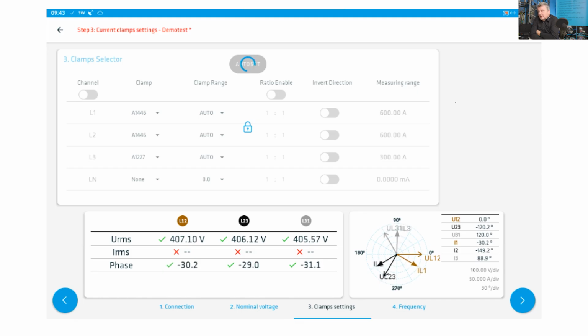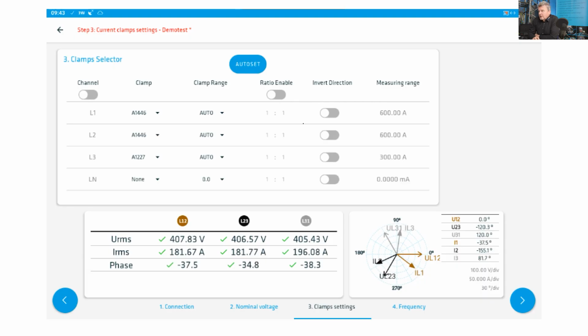This takes up to 1 minute, because the value of the current must stabilize, and we will see the final result in a few seconds. The maximum time depends on the saturation of the electronics and could take up to 1 minute, as I already mentioned. Now we'll wait for the current to be presented. When you select auto range, during the changing of the range it's possible that you will not have some results for a specific integration period, especially if you use 1 second or a period shorter than 1 minute. Now the value has stabilized and the optimum current range was selected.